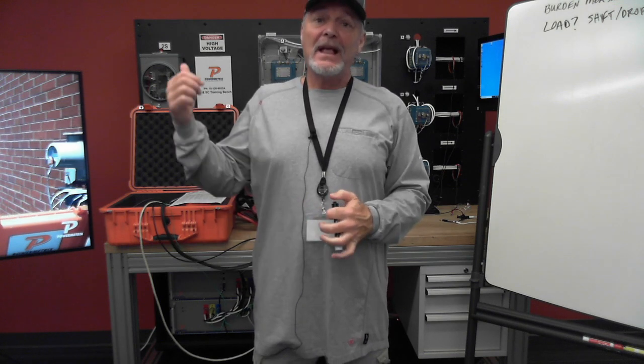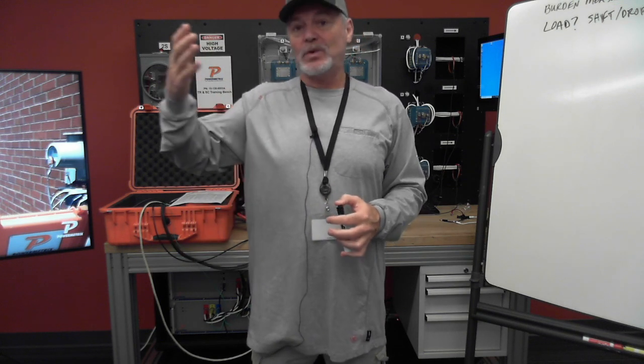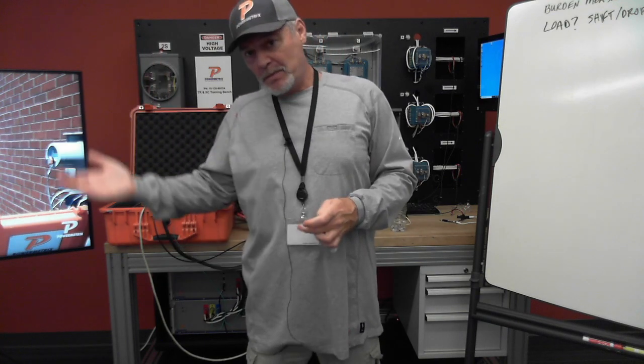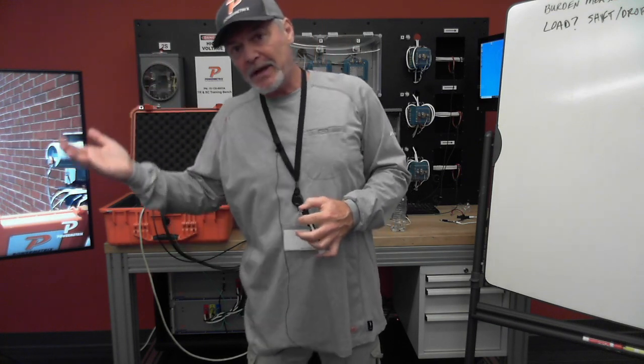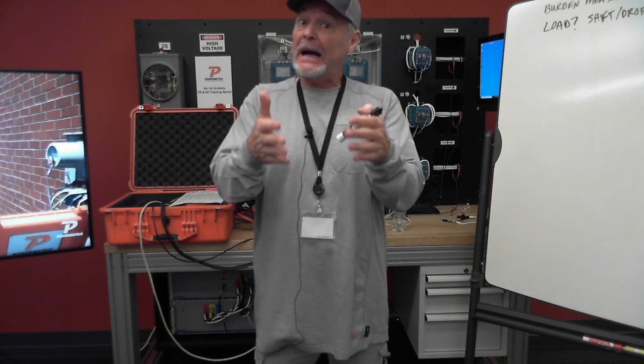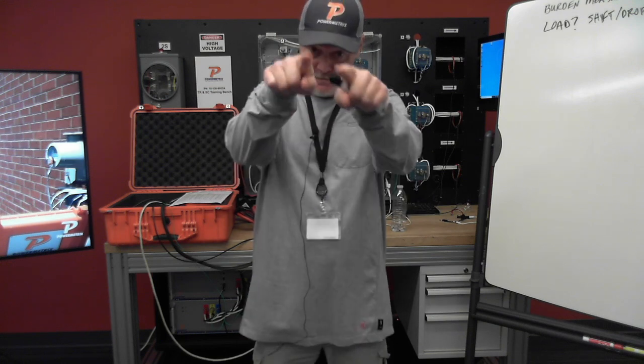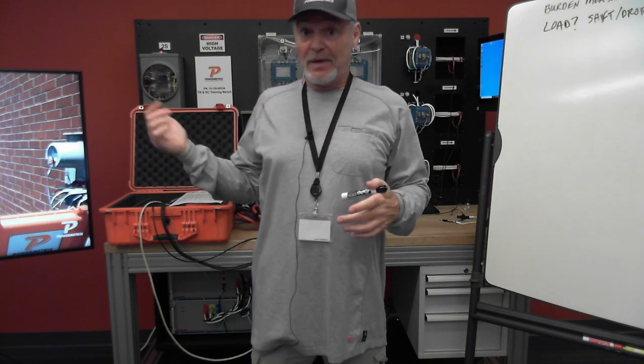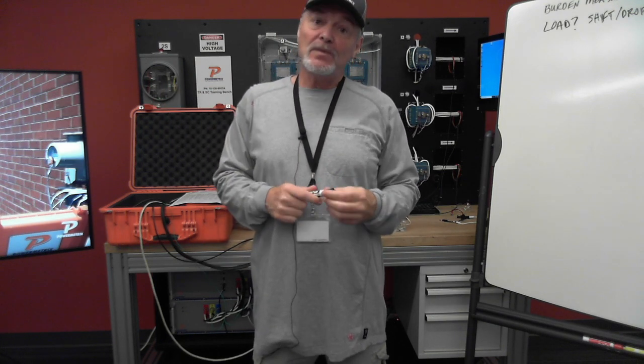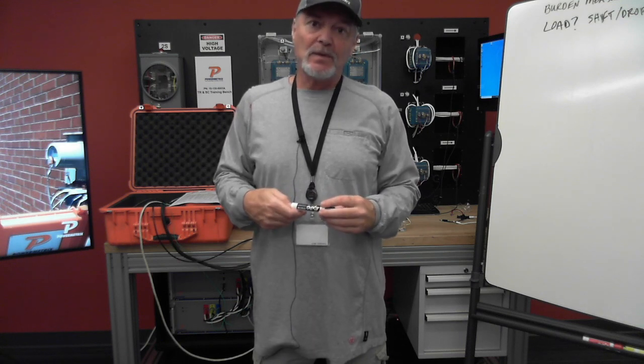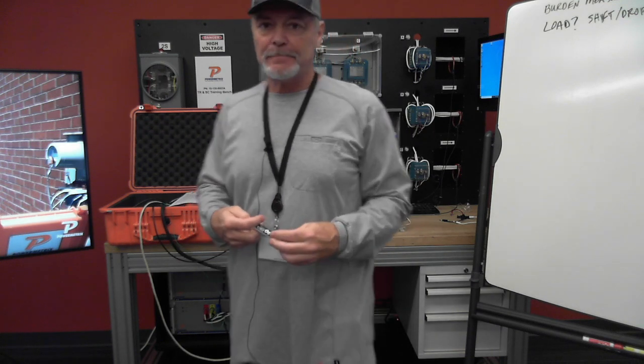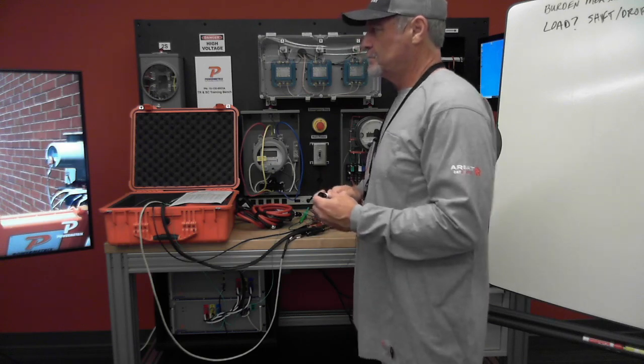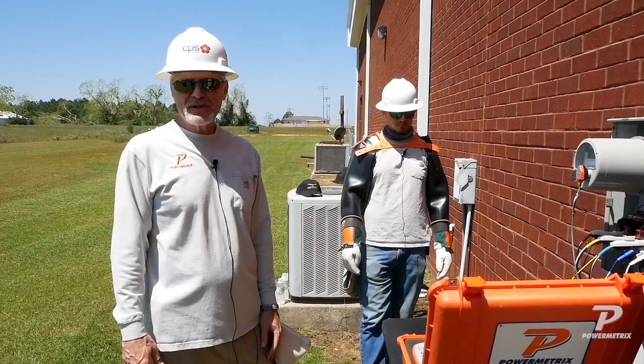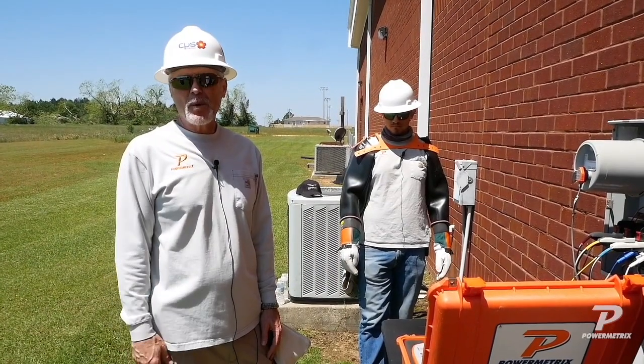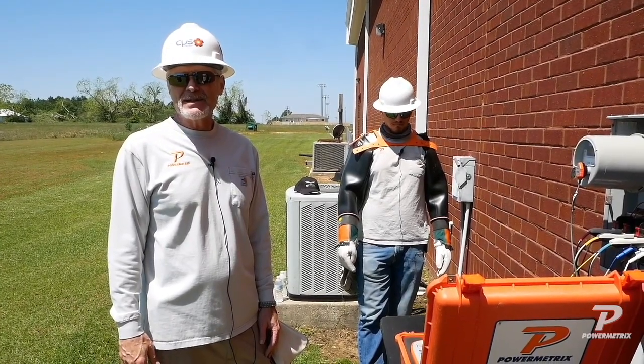And so the burden measurement test would have shown the too much resistance and burden on there, and that would have keyed us in. But then also it was the local knowledge. Once again, eyes and ears of the utility. Who is that? That's y'all. So the local guy was like, yeah, there's one more thing you ought to check. And sure enough, when we checked it, that's what we found. And we're going to talk about it here in just a second. So this would be one of them that you would bring up to the folks and report it and get them to change that out and try it out and see if that's not the problem.